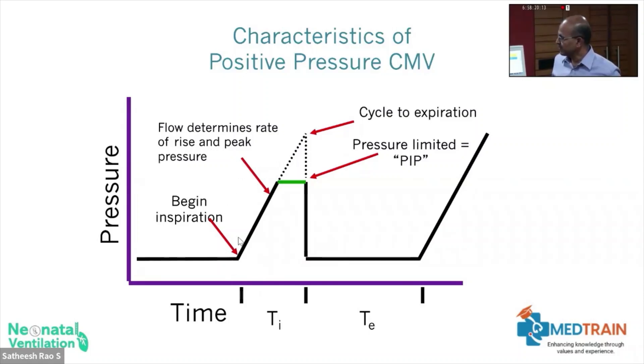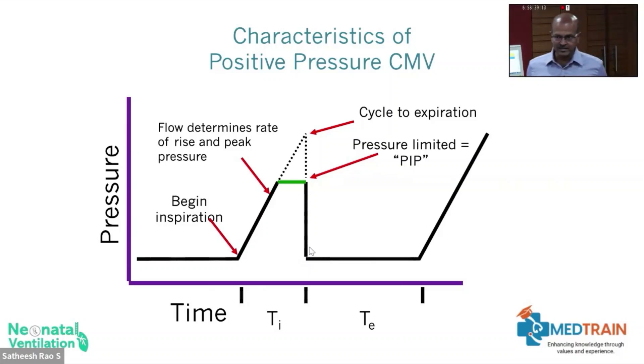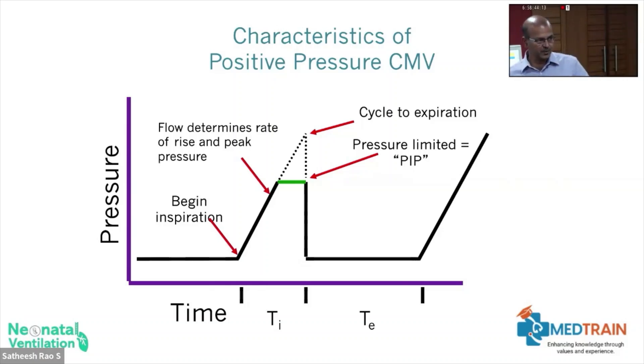If the flow is very fast — a high flow like 10 liters — you may get a square waveform. We'll come to the next slide to show that. In pressure-limited ventilation, the pressure cuts off as a plateau through the inspiratory time, then drops at end-inspiration. In modern modes like pressure support ventilation, when the patient's flow drops to a certain level — like 15% — you get the end of inspiration.